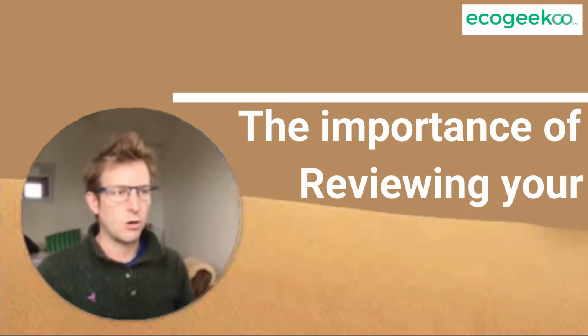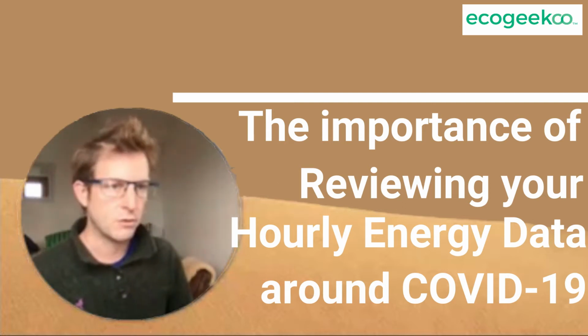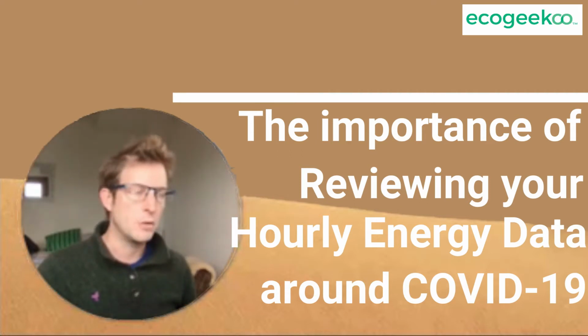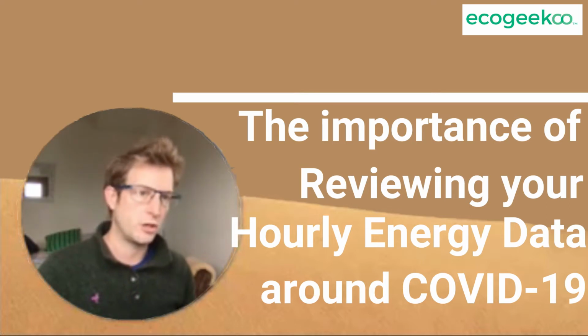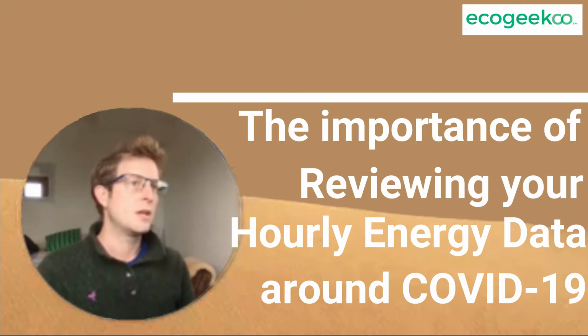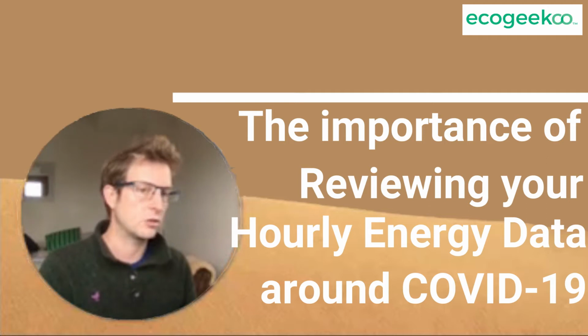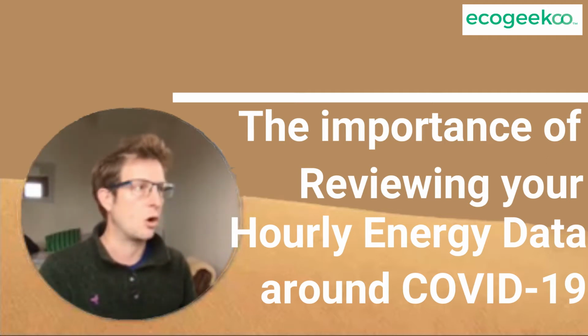Just a very quick video to show you the importance of reviewing your hourly energy data from your buildings around COVID-19. A lot of us would have shut buildings down as most staff are now working from home. So what you've probably done is spoken to your controls engineer or the people that operate your building management system, like your facilities team, and said, hey, let's put our buildings into holiday mode because no one's there. So let's shut them down to stop wasting energy and power, which has a big cost.